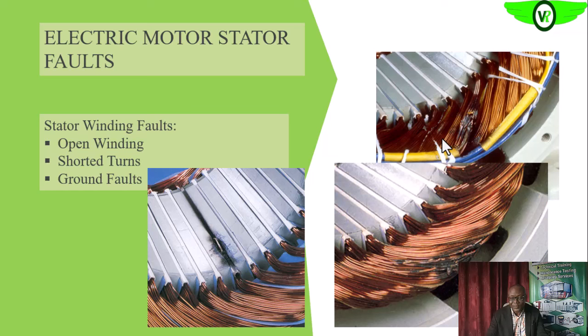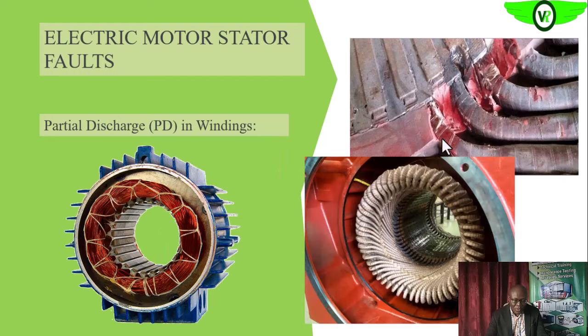We are considering the factors that can cause burning of the electric motor, and looking at the burn pattern to help identify the possible causes of the winding getting burned. Another fault associated with the electric motor is when there are shorts caused by partial discharge in the windings, which is usually caused by weak insulation.